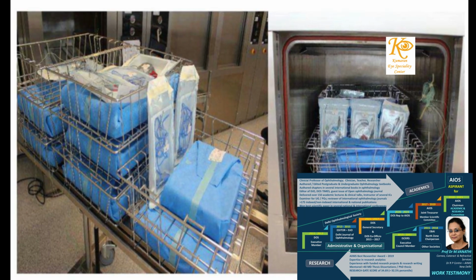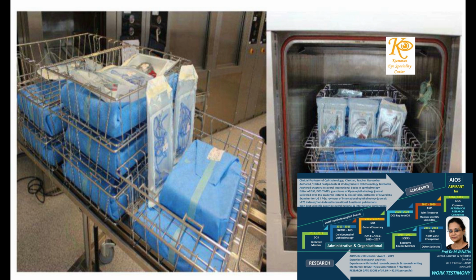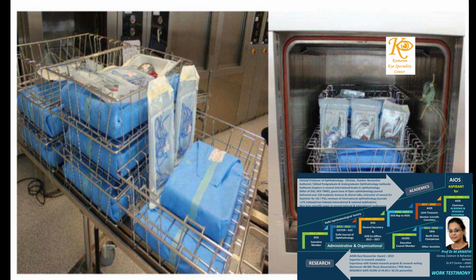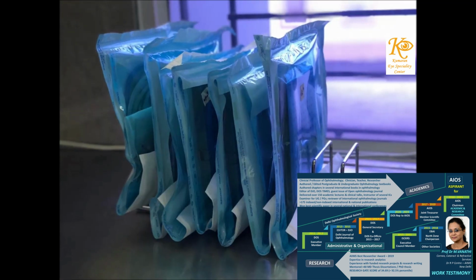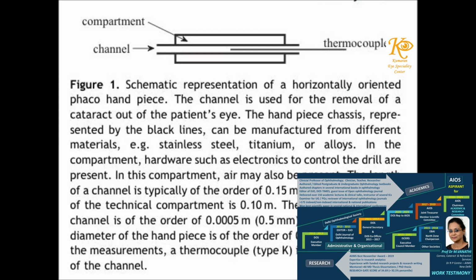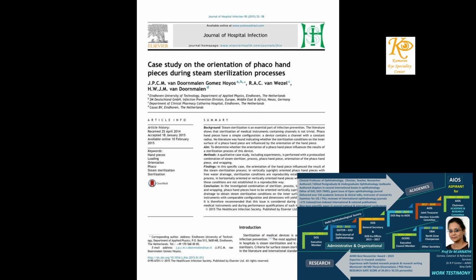Various studies have proved that the temperature inside the lumen of the phaco probes reaches sterilization standards only when the phaco probes are vertically oriented inside the autoclave, rather than horizontally placed probes, where the sterilization temperature was not reached. Hence, placing the phaco probes vertically inside the autoclave is crucial for effective and complete sterilization.